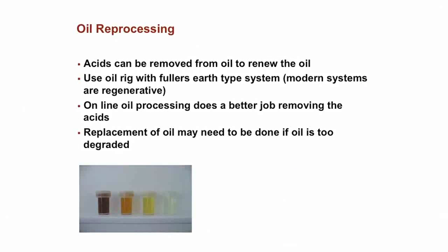Okay, then processing of oil. I talked about that. When I say processing of oil, I don't mean just degassing and dehydrating the oil. What I mean here is where you put the oil through some kind of clay system, and then you upgrade the properties of the oil back to when it was new. There are different systems for doing that. The traditional way was using a certain clay called Fuller's Earth. The only problem with Fuller's Earth is that it's disposable, so environmentally it's not that attractive anymore. Most modern ways have a regenerative clay system.